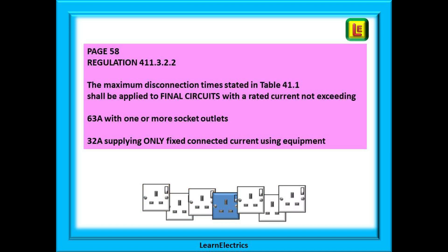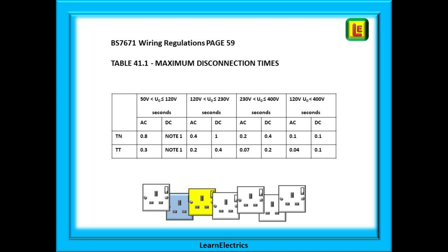Now that we know why we have disconnection times, where do we get the information from? Let's start on page 58 of the 18th edition wiring regulations book. On page 58 you will find regulation 411.3.2.2, which tells us to use the disconnection times in table 41.1 on the next page. This is for final circuits with a rated current not exceeding 63 amps for a circuit with one or more sockets, or not exceeding 32 amps for a circuit with fixed equipment.